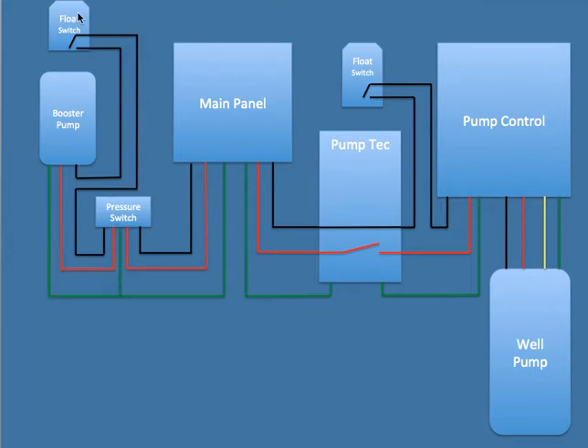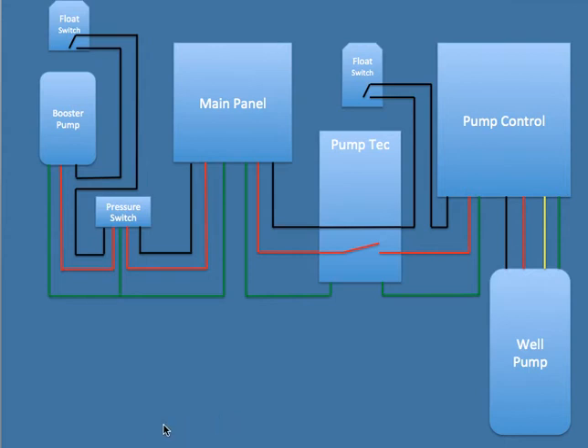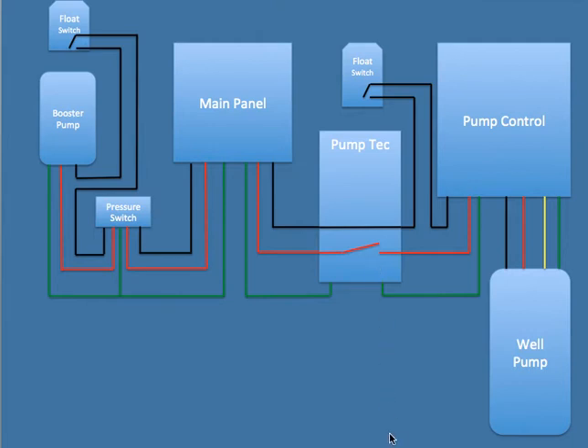Now I'm doing the same thing here with the float switch, and what I'm doing on this side is running a wire all the way from the storage down into the system and then out over to the pressure switch because I want the booster pump to be protected when the storage tank is low.